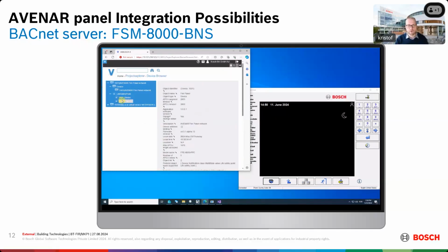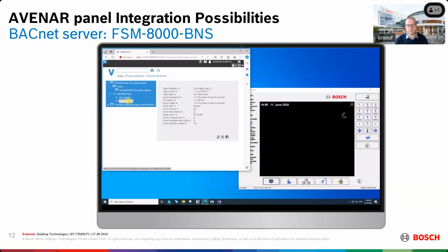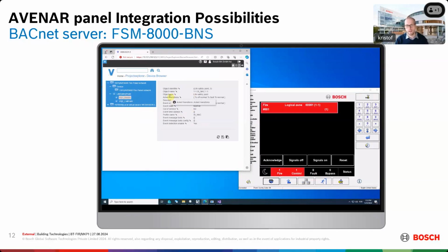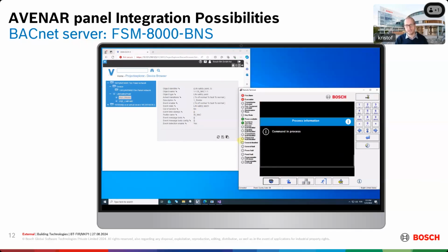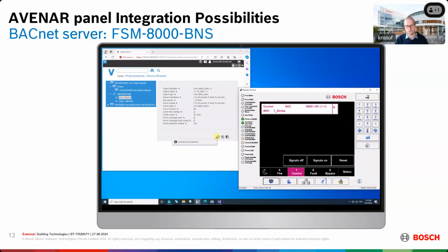You have here the strobe and the call point. As you can see, these are all objects which are standard to BACnet. If you now create an alarm on the manual call point, you will see the manual call point provides you the event state life safety alarm. Also, the strobe is now activated, so it's providing you life safety alarm. If we now do a reset of this alarm, you will see they go back to normal mode.